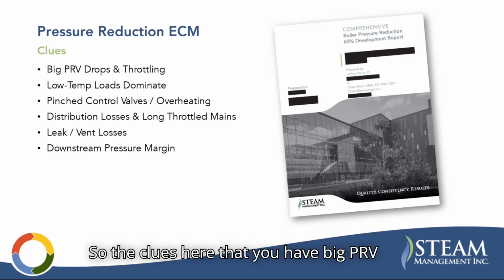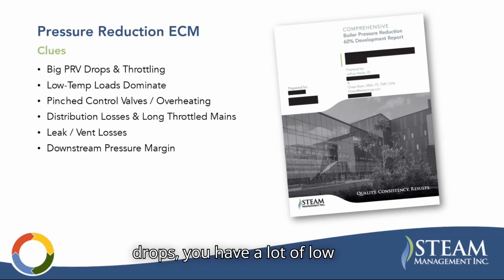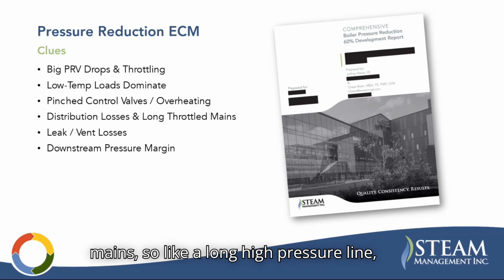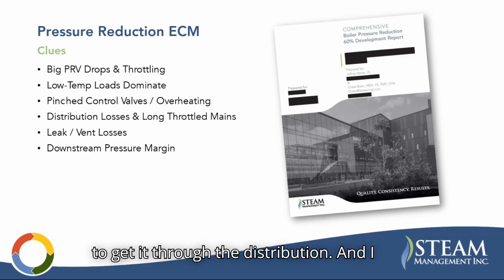So the clues here are that you have big PRV drops, you have a lot of low temperature loads, you have pinched control valves or overheating, distribution losses and long throttled mains. So, like a long high pressure line and then it's throttled down and all the users are on low pressure, and you're really only generating high pressure to get it through the distribution.